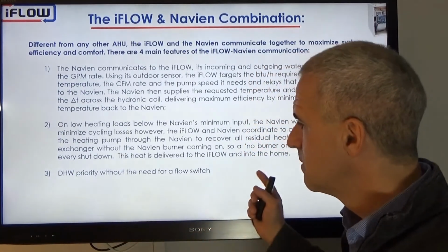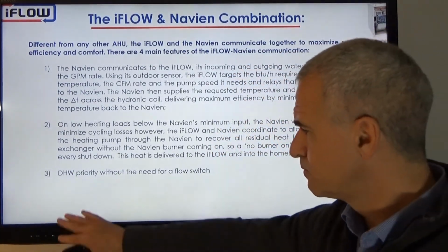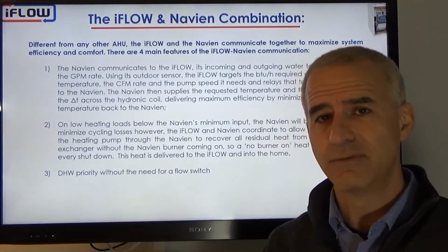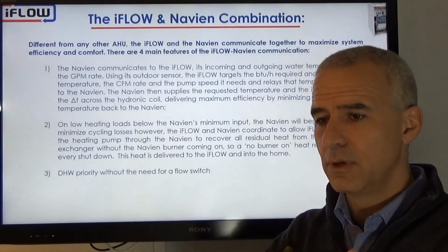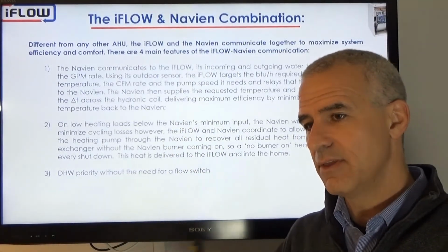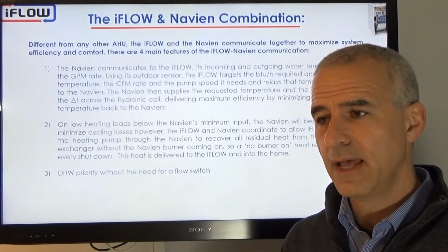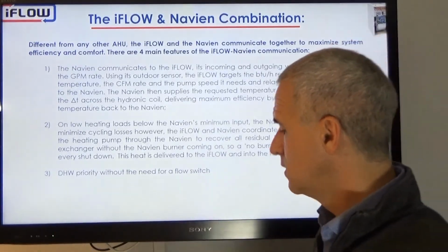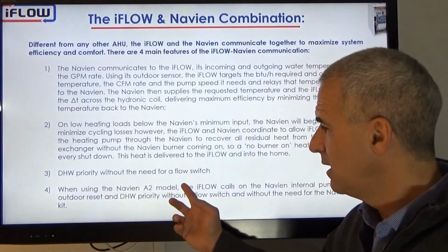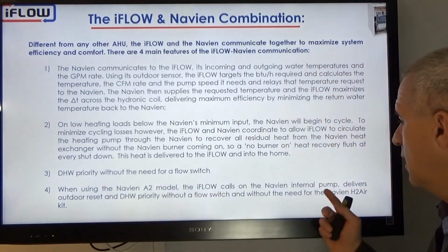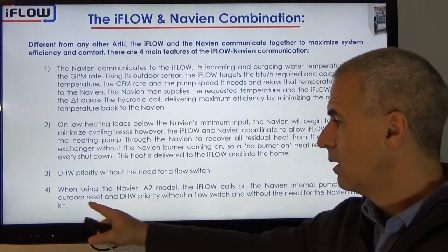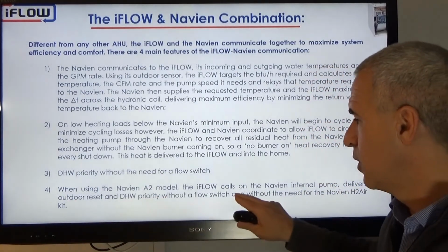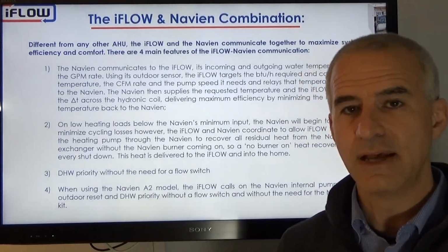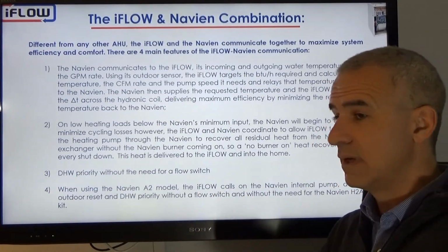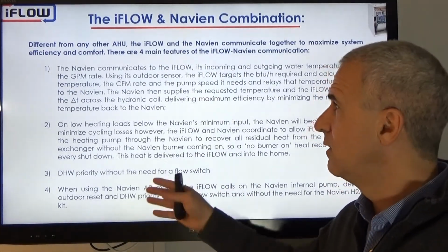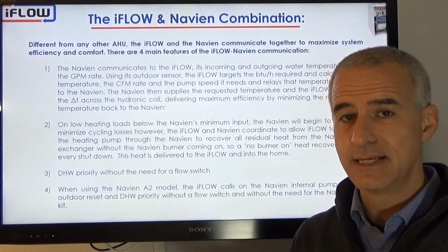by minimizing the losses. The next is we can get domestic hot water priority without the need of a flow switch. The Navien iFLOW communication is such that when we're talking together, we can determine when there's a domestic call and we'll stop the heating. So we prioritize between the two. And then when using the Navien A2 model, the iFLOW can call on the Navien internal pump, deliver the outdoor reset and domestic priority without a flow switch, and all without the need for the Navien H2 Air kit. Right? With any other air handler, you would need an H2 Air kit to run with that. With the iFLOW Navien, you have a communication cable that does that and takes care of it for you.